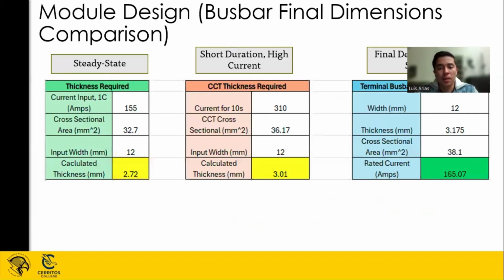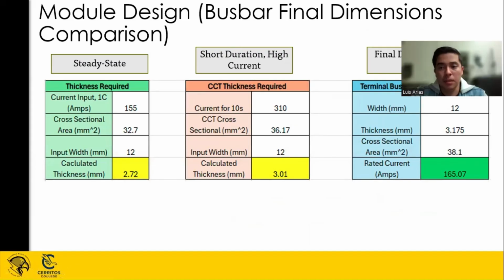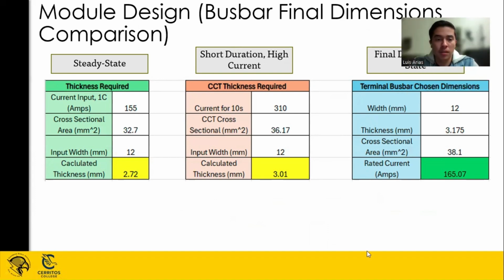To determine our final bus bar design, shown in the table on the right, we compare our final parameters: a width of 12 millimeters and thickness of 3.175 millimeters, chosen to be available off the shelf. This gives a cross-sectional area of 38.1, capable of a rated current of 165 amps, which is above the 1C rate. Thus, this dimension will be useful and proper for our battery design.